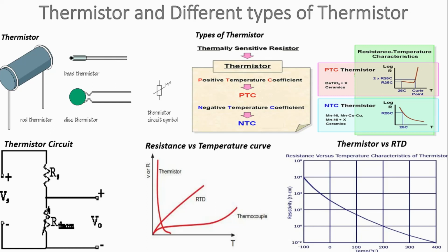Another major difference is in the operating range. Due to their high sensitivity, thermistors are used in narrow span measurement and low temperature ranges from -20 degrees Celsius to +120 degrees Celsius. But RTDs are used worldwide and for larger temperature ranges. Now we will also see how the construction looks.